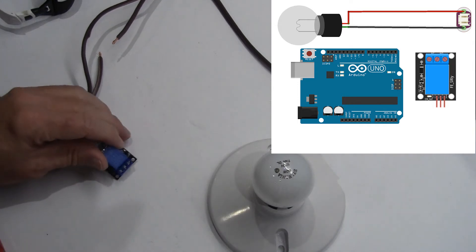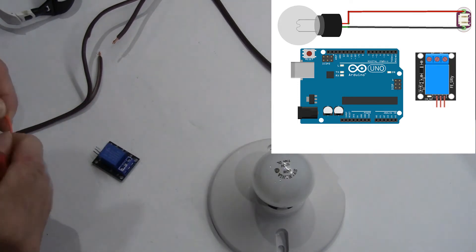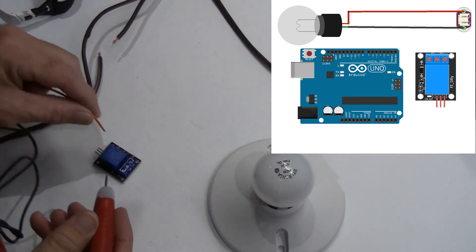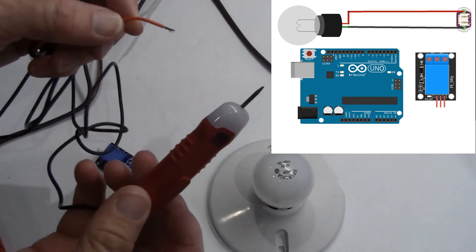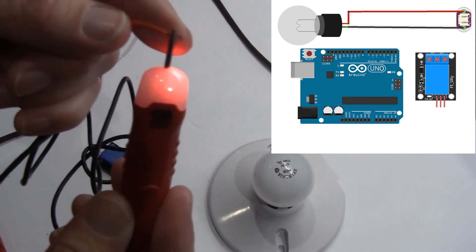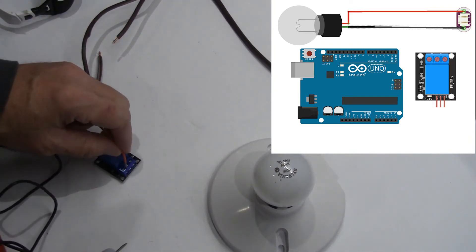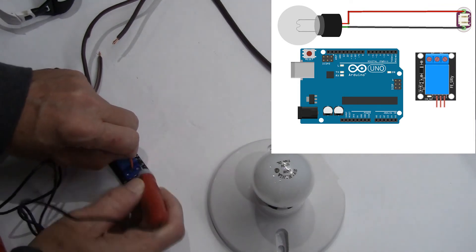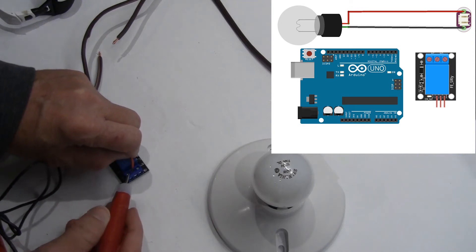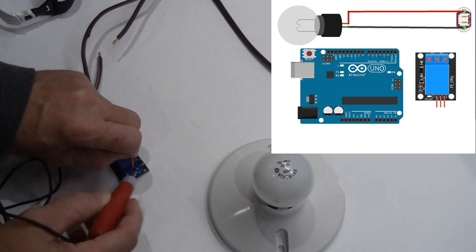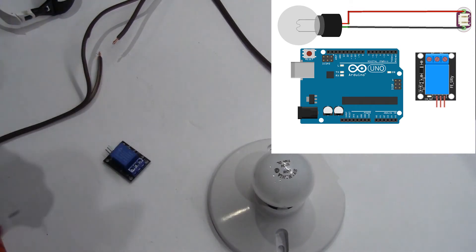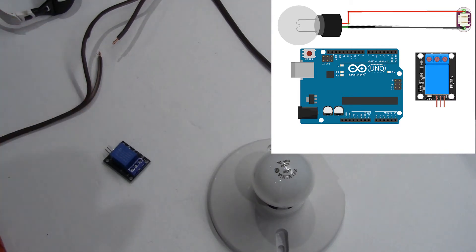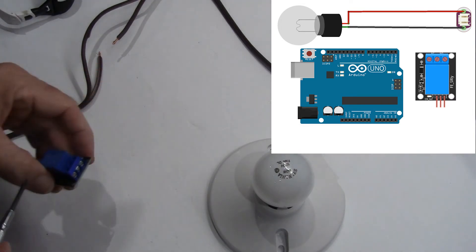Sometimes these relays are labeled for us showing us where the common and the normally open and normally closed terminals are. But this one is not. So we're going to do a little test here using a continuity tester. As you can see here, when these are connected, it lights a light, which lets us know that those are connected. And we can test to see which sides are connected at a resting state and which aren't. The middle is usually common. And if I use this and connect from the middle to the left, I can see that that is a normally open switch, where to the right is a normally closed switch. So in our design, we're going to want to connect this to the normally open switch.